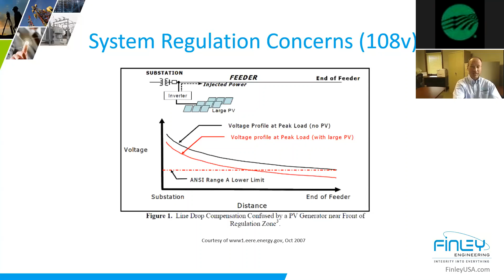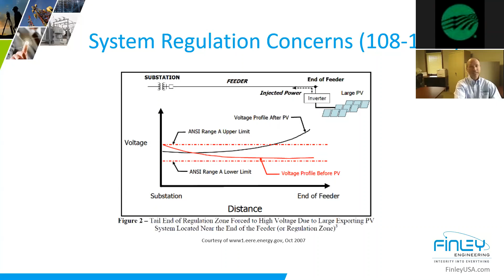So let's do the inverse of this same discussion now, and let's inject the PV source at the end of the feeder. So look at the potential. I've shown you both in red, the upper and lower limits there. We can see the 108 to 126. And in red, you're seeing what would have been the normal profile. But look at the potential for in-line voltage elevation due to a source and this regulator possibly stepping down or not stepping due to its impact, and you could end up with a tail out of zone regulation voltage issue. Like I said, usually it's an eye opener with people that they don't even realize this potential can exist. Especially then you've got multiple sets of coordination between different sets of regulation, which could be exacerbated by that potential. So I'm just bringing up some of these. We're going to talk about mitigations toward the end.